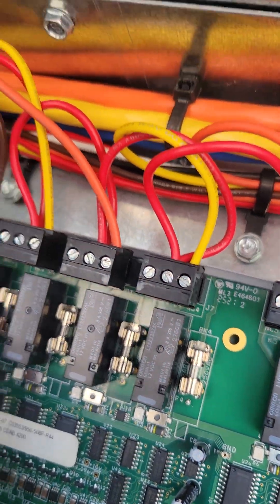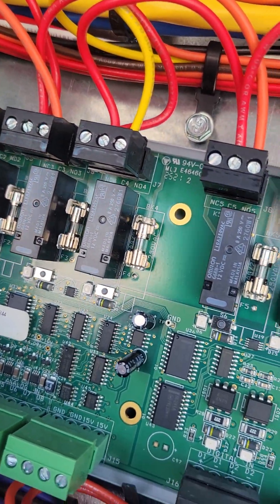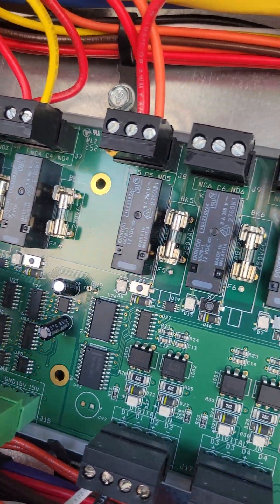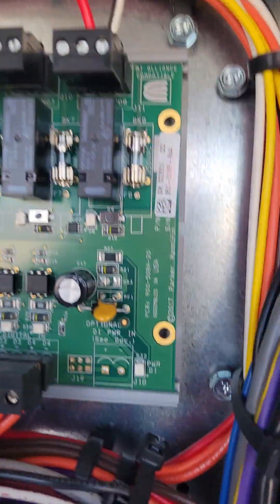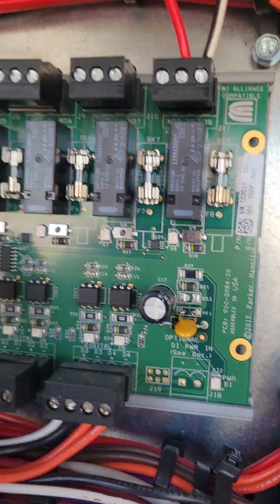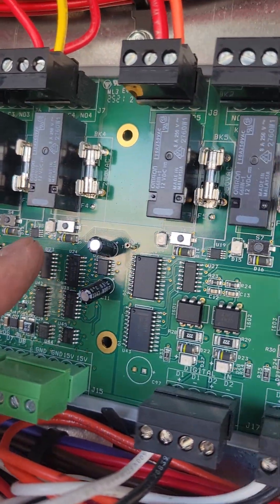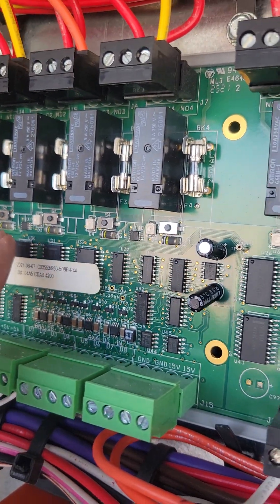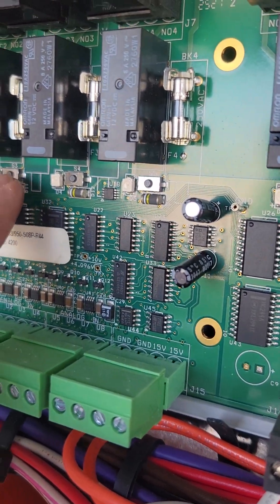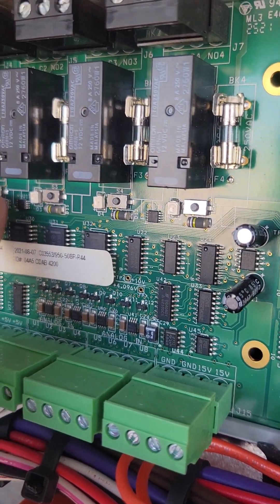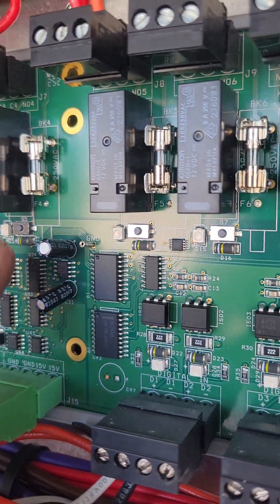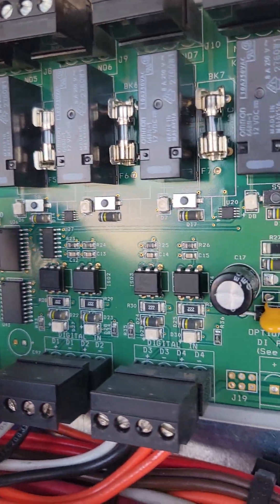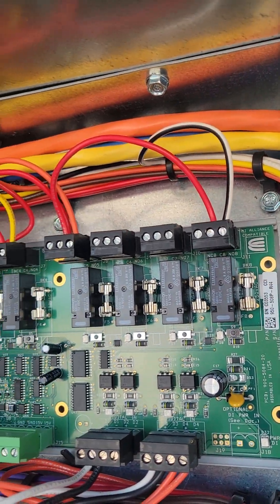These digital outputs also have lights associated. These are little amber lights. I believe these ones are green. Well, they might be amber as well. And they also have these little override buttons. Those are momentary override switches which you can hit with a ballpoint pen or something like that to test it.